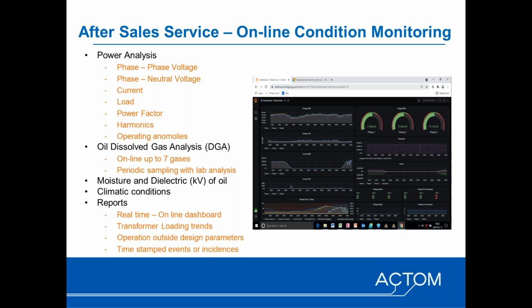We look at the power that is put through to the transformers. We can add dissolved gas analyzers on the units, and we factor in the climatic conditions in that area. With this we've got real-time online dashboards where we look at the transformer, look at the loading trends, and alert customers to possible trends indicating something could be wrong with the transformer.